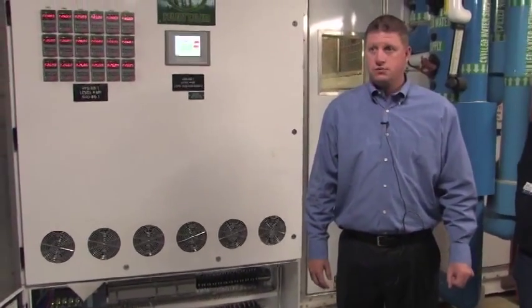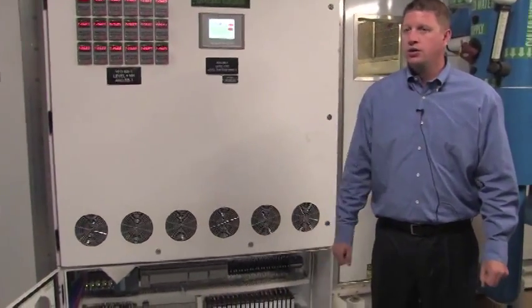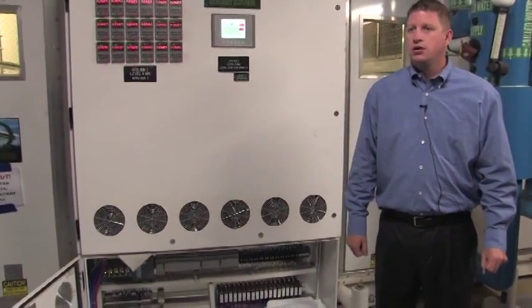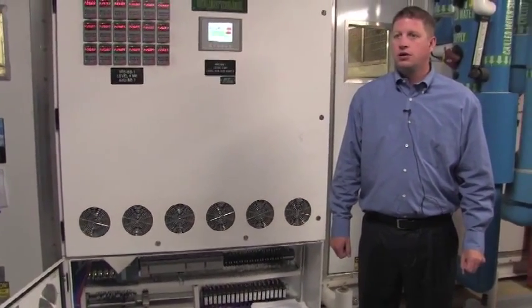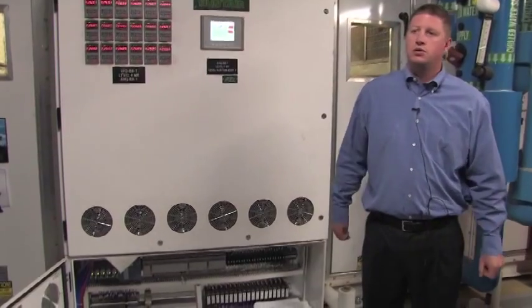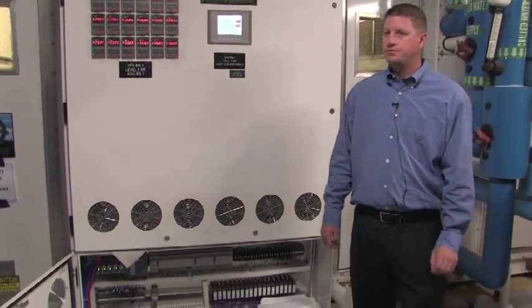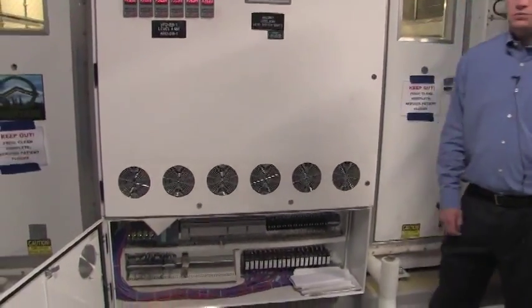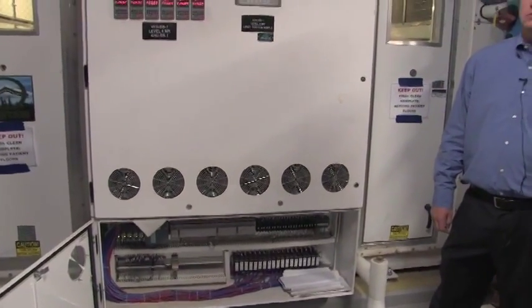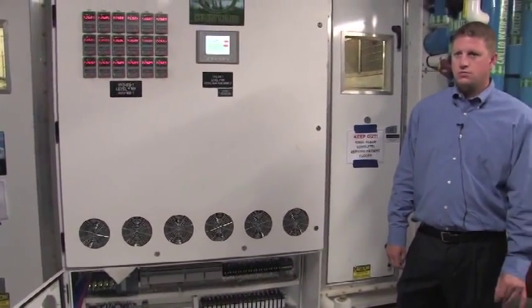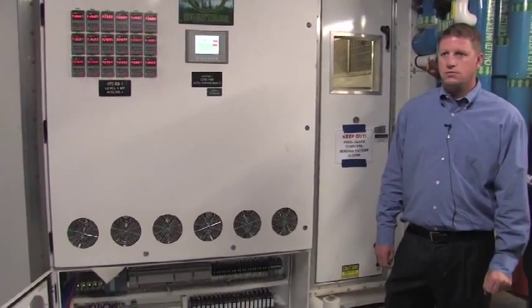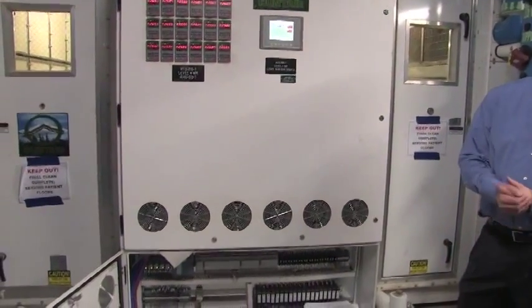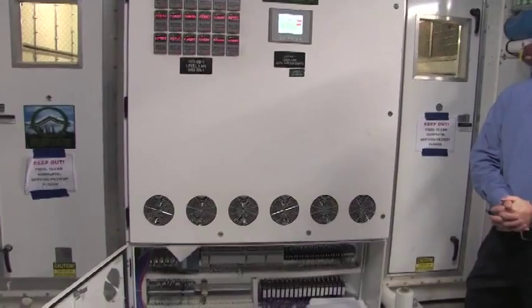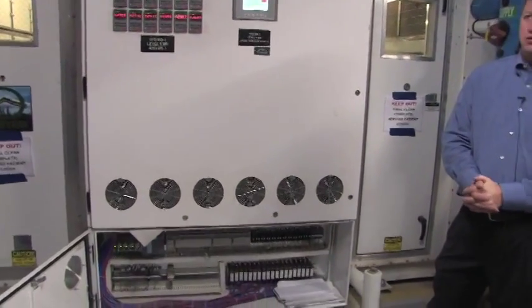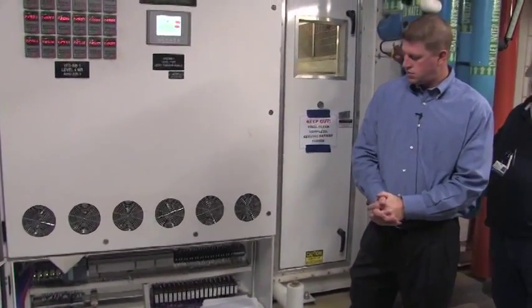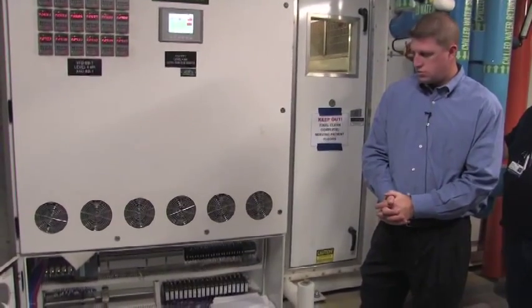That's the safety relay. Only that relay will be lit when all the safety circuits are good. You trip off on a smoke, low limit, high limit, low static, high static, that will drop out. If that's not lit, your unit will not run. And that's coming from us. When I do my side of it, I'll explain that. But that's what that relay is. And it's marked here. It says FAS safety relay. Is that relay out?